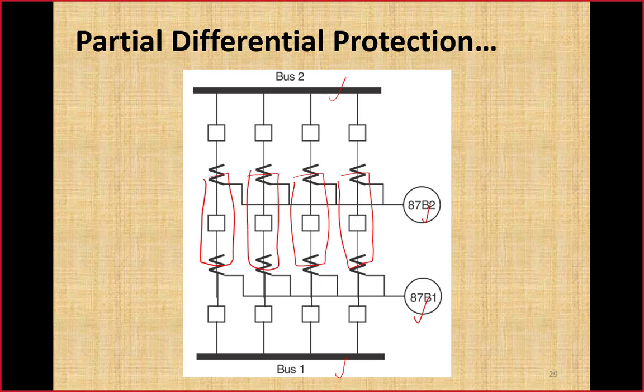That will be part of line protection because lines are connected here at these points, and line protection will cover this portion, which is between two bus bar protections. Because when a fault occurs here in this section, no need to trip any of the buses, only line protection should operate and open this circuit breaker from here and from the other end.